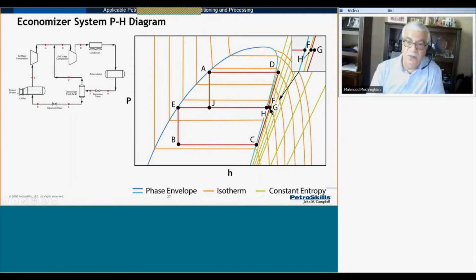Then I do mixing with the vapor coming from the separator, which is cooler, add it to the discharge of compressor, which is warmer, and then go to the second stage of compression. And then for second stage of compression, I go from point F to point D. So again, similar to previous case, I know the chiller duty, I know HP minus HC or HC minus HP. I get the mass flow rate, I calculate power requirement for this first stage, and I can determine the mass flow rate through the second stage, which is higher.